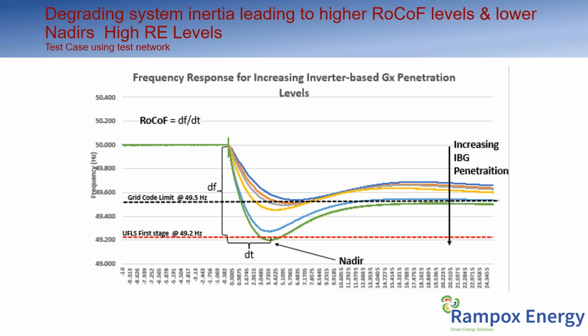So if you look at that phenomenon while increasing penetration of renewable energy, in terms of the nadir, that is the turning point — remember the Grid Code reliability requirement is to turn at 49.5 — as you increase renewables while keeping the same amount of reserves, you start seeing that your nadir falls. That means you need to recalculate, as the system changes, how much reserves you're supposed to carry so that you still observe the Grid Code. Otherwise you start violating it.